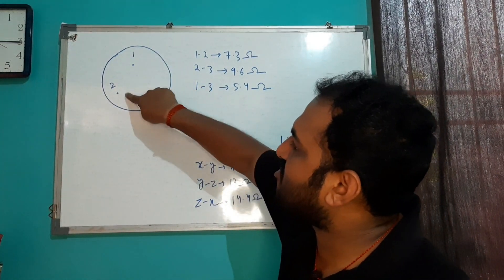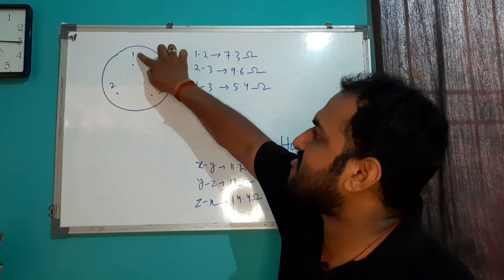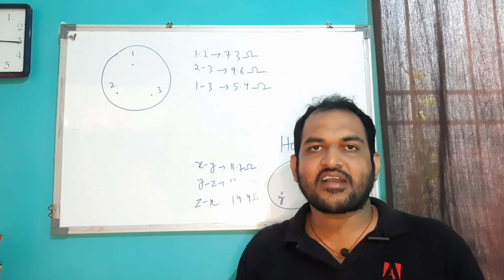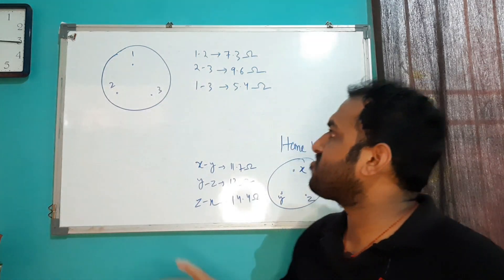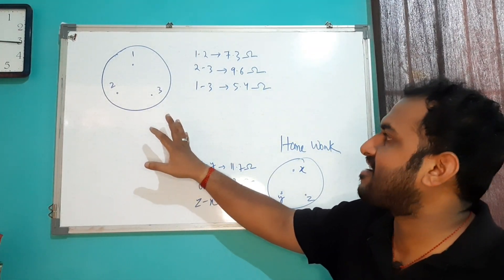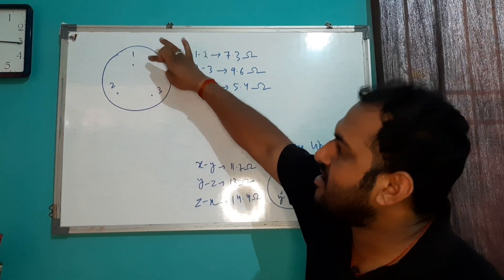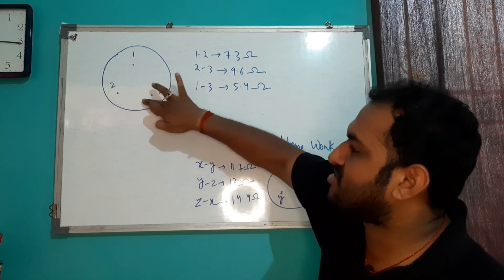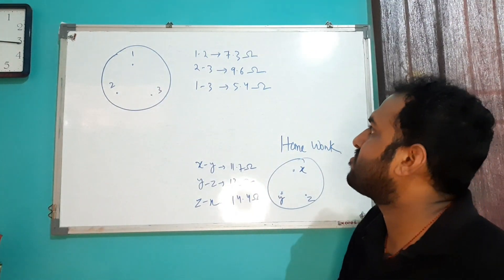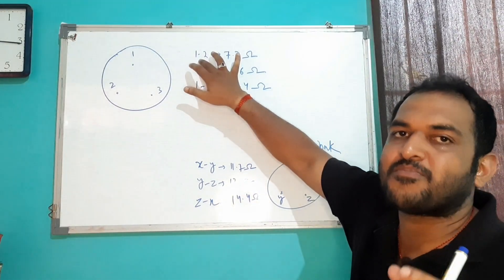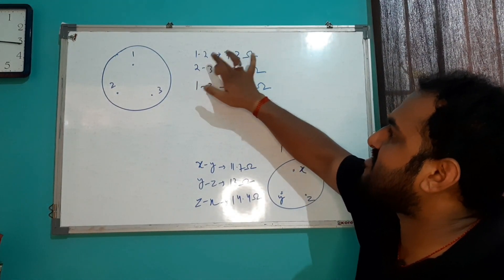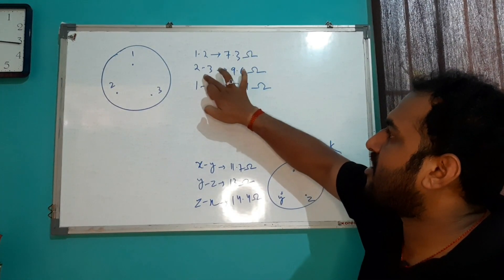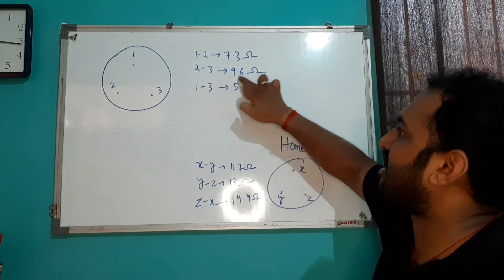Suppose this compressor has 3 terminals. I will name them terminal one, terminal two, and terminal three. First, we need a multimeter. We have to measure resistance across terminals one and two, then across terminals one and three, and similarly across terminals two and three. The resistance across two and three terminals is 9.6 ohms.